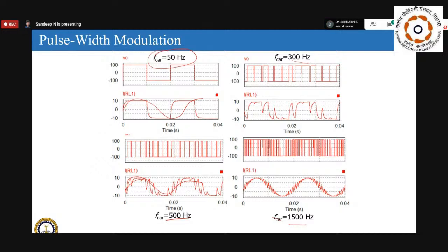Then at 1.5 kilohertz, you can see it is very near the sine wave on an average basis, with ripple around it. So as you increase the carrier frequency, the current becomes more sinusoidal, but at the cost of increased losses in the inverter, because no practical device has zero losses - there is a loss at every switching. So the more you switch on and off, the higher the losses. This is a trade-off: depending on filter size and loss, you must find an optimum value where both are satisfied.